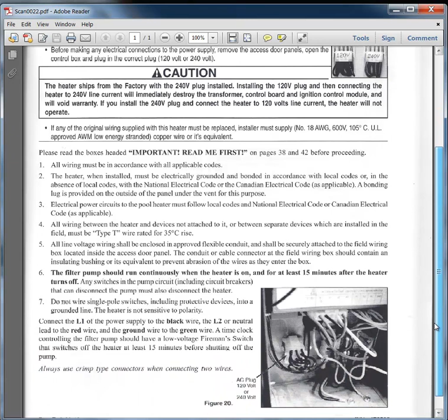What it does: it disconnects the fireman switch, turns off your heater, leaves your pump running for 15 minutes. The reason why is to cool off the heater. If you just arbitrarily turn off the heater, all that heat from it burning for 2 or 3 hours is just sitting there, so that copper is just starting to twist and burn and make holes and all kinds of things. That's why they want 15 minutes.